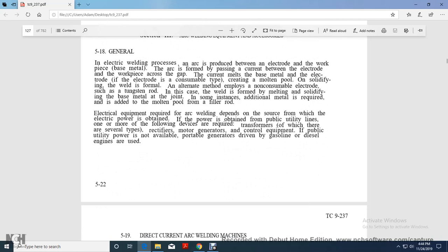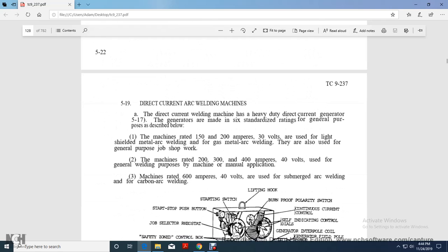The electrical equipment required for arc welding depends on the source from which the electrical power is obtained. If the power is obtained from public utility lines, one or more of the following devices are required: a transformer, for which there are several types, a rectifier, motor generators, and control equipment. If public utility power is not available, power generators driven by gasoline or diesel engines are used.